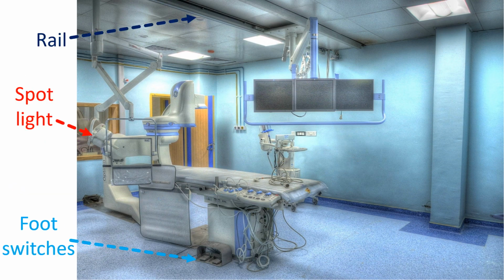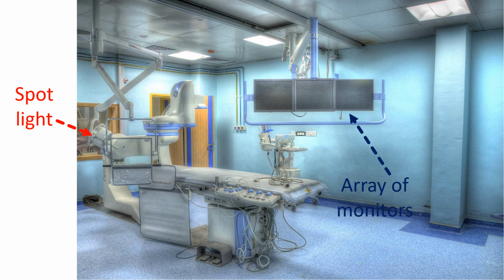In the system shown here, the movement rails are mounted on the roof. There are also systems with rails for some equipment mounted on the floor as well. Foot switches are there to control the X-ray source to decide whether you want the low radiation continuous imaging, usually called fluoro mode, or the short cine runs of high radiation for high contrast images. The system usually gives a different audio alert while on cine mode. A roof mounted spotlight gives illumination at the external procedure site for skin puncture and device introduction. An array of monitors is also roof mounted here. It can be moved closer to the operator when needed.